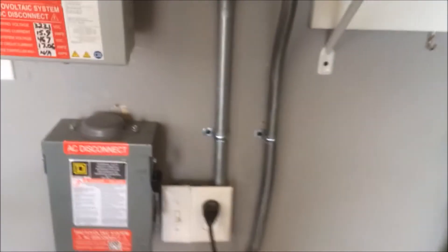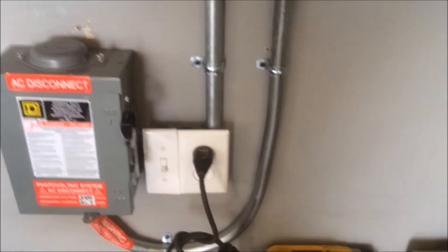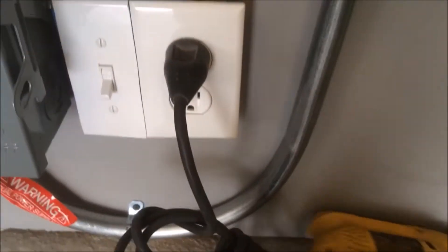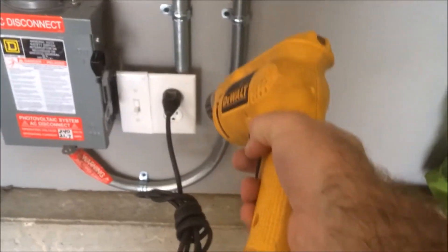I finally got around to wiring up the off-grid circuit to this grid-tie inverter. This inverter has a neat little option: when the power goes out and the grid goes down, a secondary dedicated off-grid circuit can kick on and put out up to 1500 watts at 120 volts, versus 5000 watts at 240 grid-tied. So that's a neat little option — let's try it out. Here we've got a dedicated outlet going straight from the inverter to this outlet.